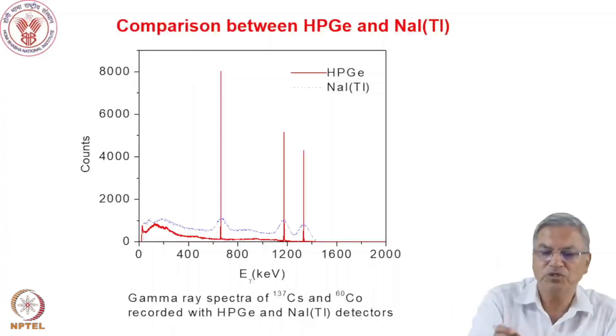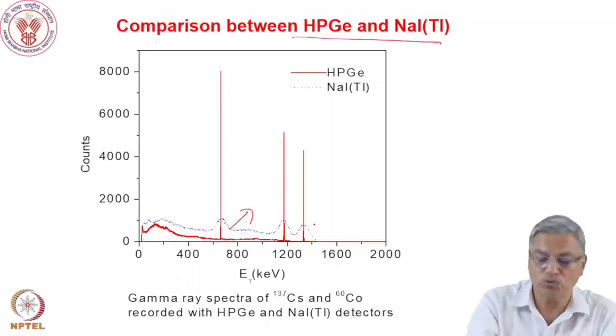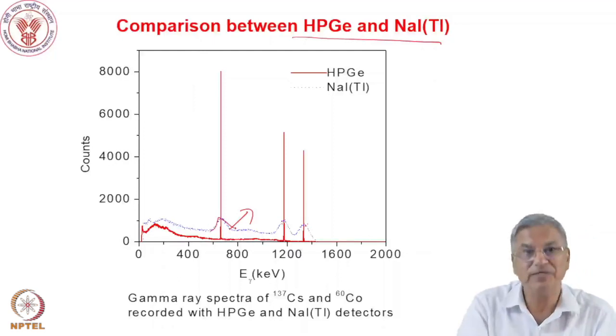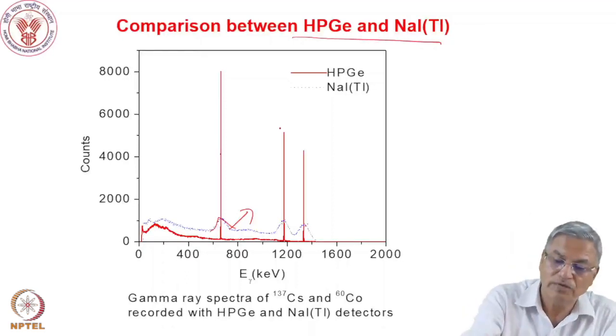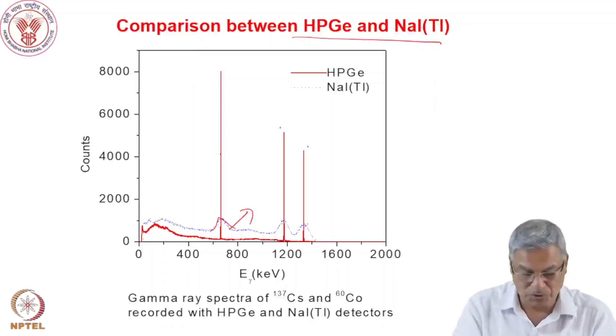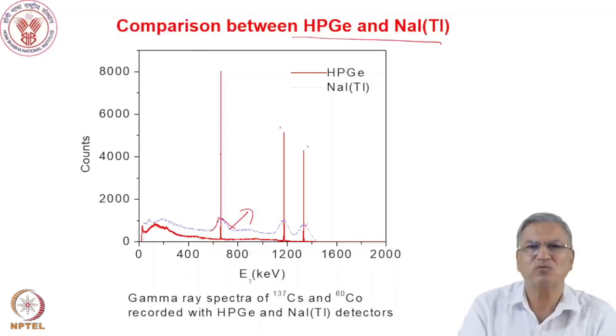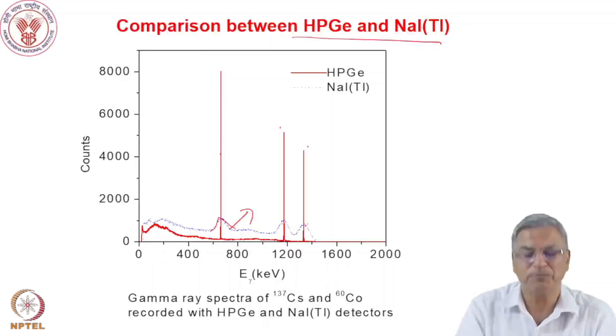Comparing gamma ray spectra of sodium iodide thallium and germanium detectors using Co-60 gamma rays at 1172 and 1332 keV, the germanium detector shows dramatically better resolution than sodium iodide thallium. For gamma spectroscopy, you always prefer germanium detectors. However, germanium detectors cost approximately 15–20 lakhs, compared to 2–3 lakhs for a sodium iodide thallium detector, so the choice depends on the required information — if high resolution is needed, go for germanium.